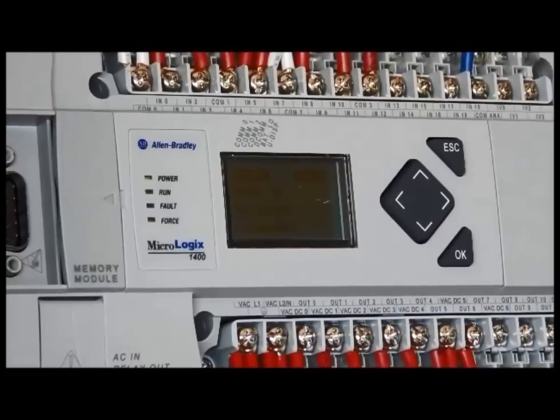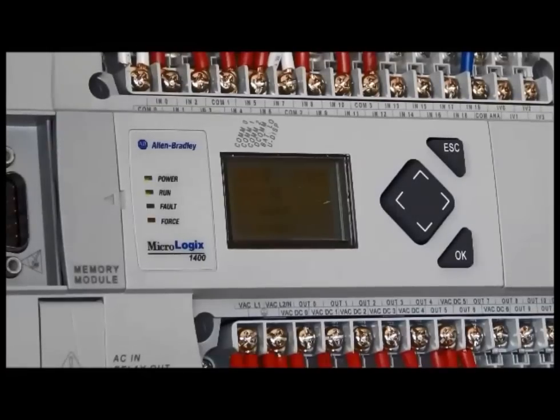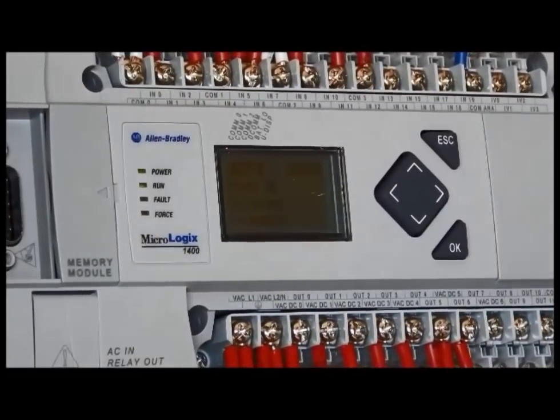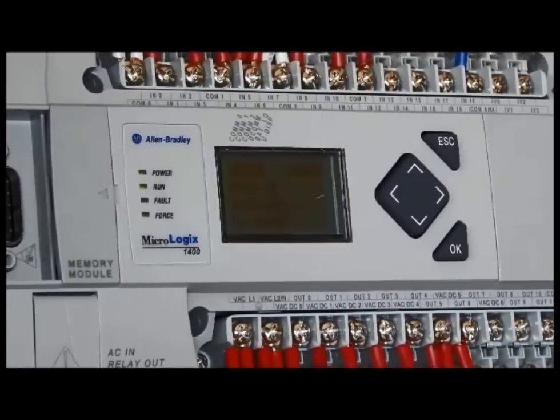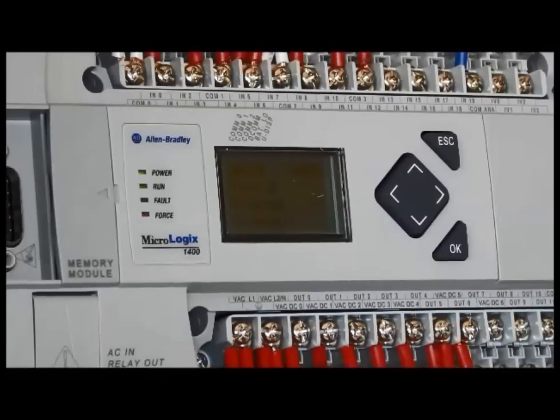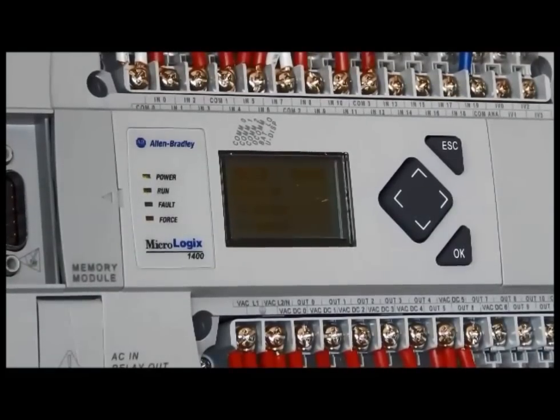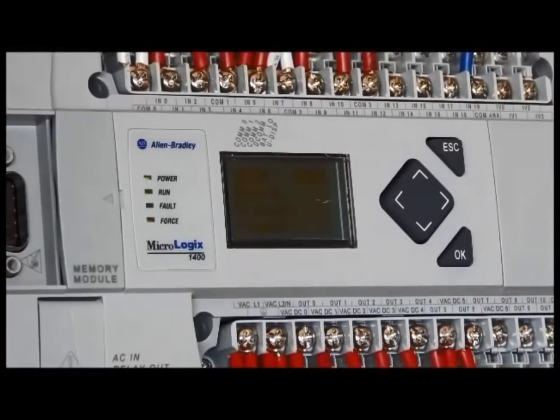The processor also has a user interface — a gray LCD screen that passes information on to us and allows us to interact with the processor. To the left of that, you will notice some very important indicators. The top green light is power, indicating the unit is energized. The second green light is run, meaning the processor is receiving and passing on information when a program is present. The third light, when energized, will be red and indicates fault — when the unit has faulted, it will neither receive nor pass on information. The bottom light is forced, shown in amber, and is on strictly for the purposes of this video; in normal operation it will never be energized.